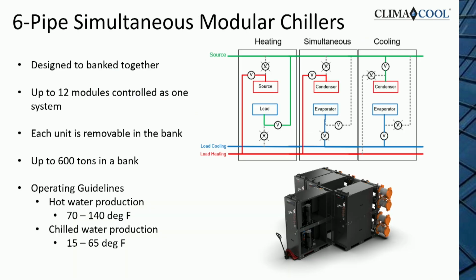So that's just a little bit more about the 6-pipe simultaneous. You take that mixing of the water between the source and the heating and cooling loops, and then you scale it and put multiples of those together. And really, you can pretty easily get up to 600 tons. Not saying that's the fine limit. That's just probably the typical limit based on what's coming out of the factory. But I think 600 tons gives you a pretty broad range of buildings that you can cover. You can also do multiple banks if you wanted to get more sophisticated.